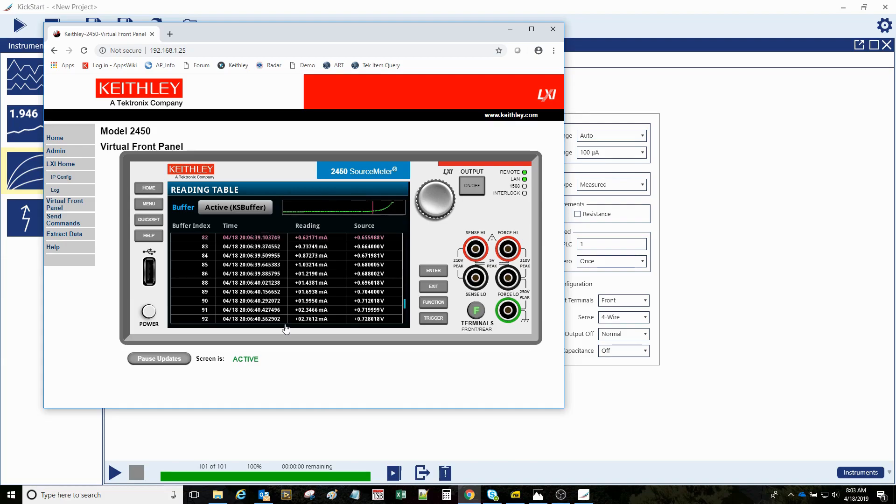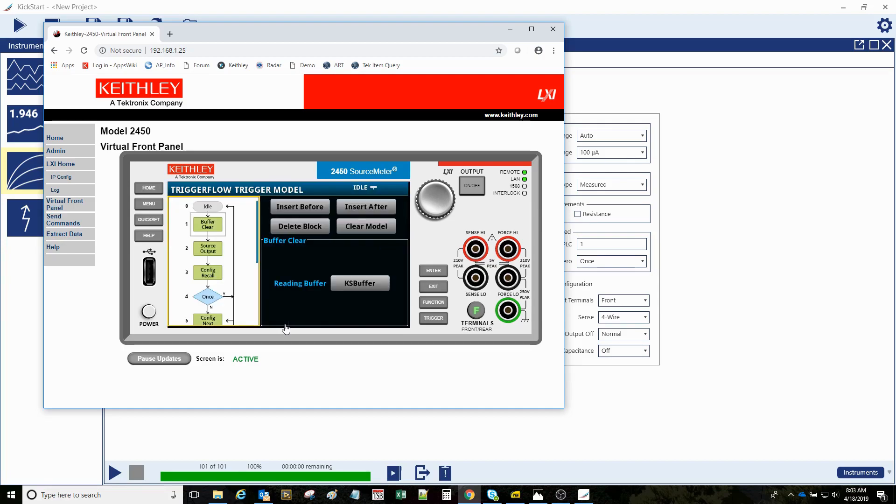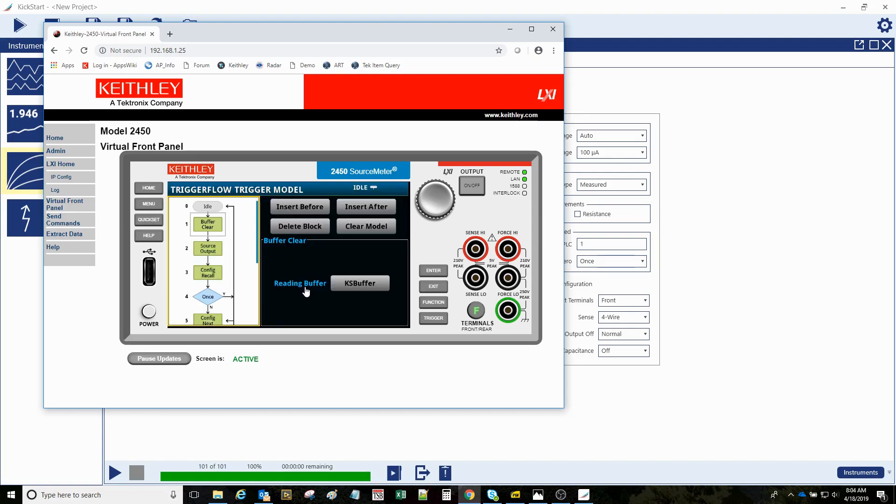If you wanted to see what was really set up on that instrument by the kickstart software, you can see this trigger model. So again, that's under menu, under the trigger column. Look at the configure, and so when the program runs, it clears the buffer.